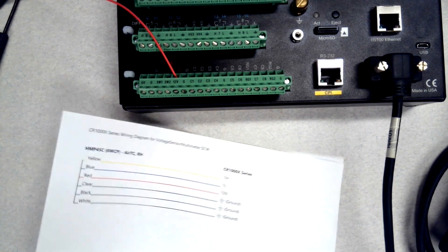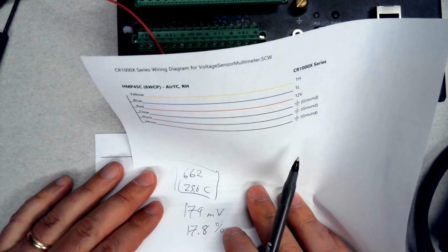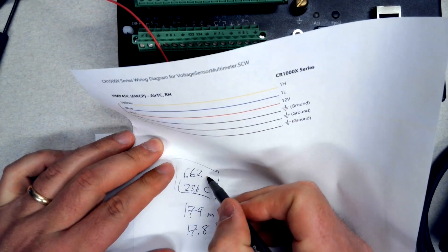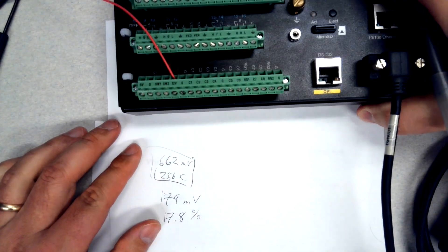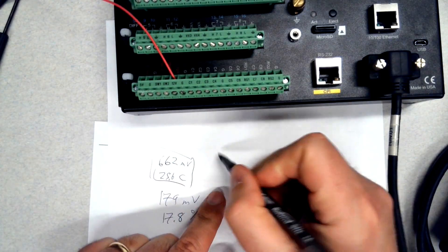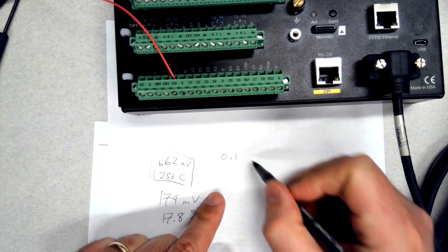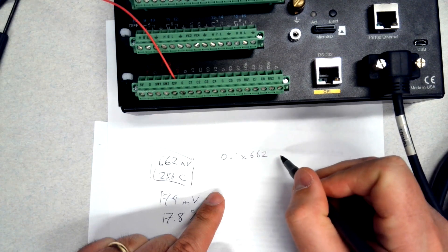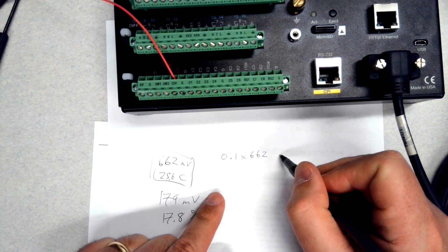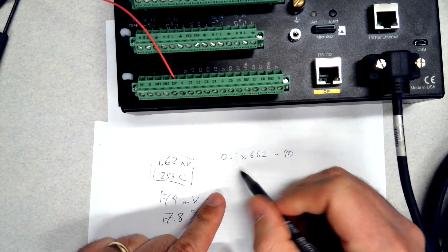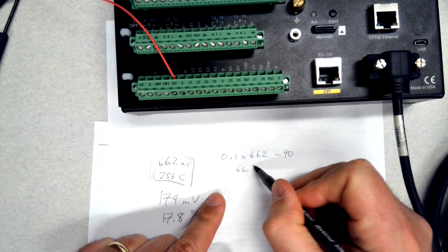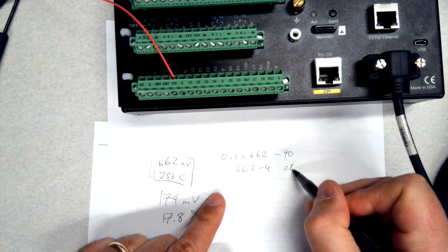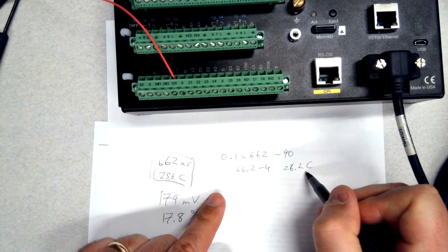Let's convert the readings. I have 662 millivolts. You need to know the multipliers and offsets for your program. In this program, the temperature has a multiplier of 0.1 and that will be times the 662, and it has an offset of minus 40. So that would be 66.2 minus 40, which would be 26.2°C, which is pretty close to the data logger measuring.